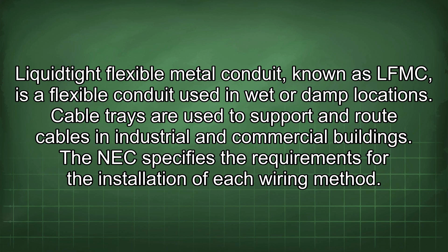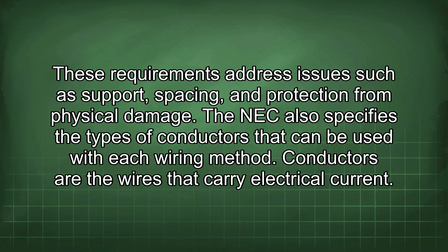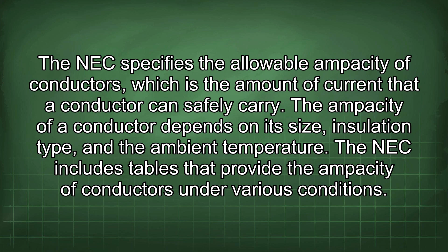The NEC specifies the requirements for the installation of each wiring method. These requirements address issues such as support, spacing, and protection from physical damage. The NEC also specifies the types of conductors that can be used with each wiring method. Conductors are the wires that carry electrical current. The NEC specifies the allowable ampacity of conductors, which is the amount of current that a conductor can safely carry. The ampacity of a conductor depends on its size, insulation type, and the ambient temperature. The NEC includes tables that provide the ampacity of conductors under various conditions.